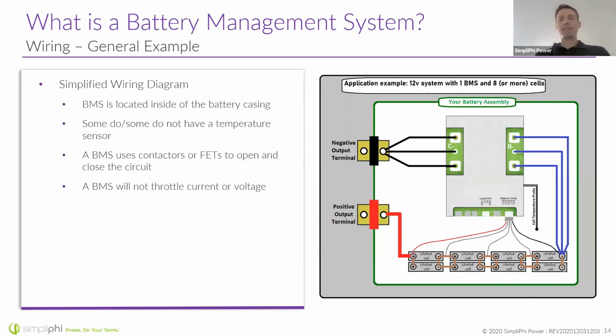Here's a simplified diagram of a BMS. This isn't the BMS we actually use in our systems, but it shows what one might look like. It shows the connection to the negative terminal, the common minus on the BMS unit, and also a connection to the battery side, running through the cells. The cells are arranged in series. This is an example of a 4S, meaning 4 in series. There are 8 cells here, but they're joined in sets of 2, so 4S means 4 sets of series.